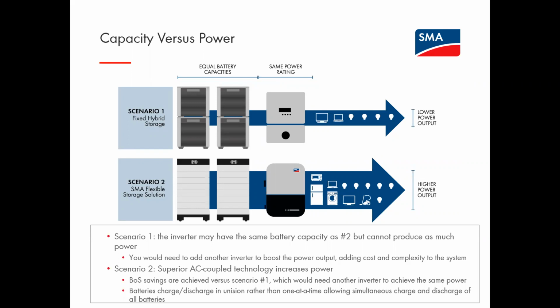So if you were to try to get more power out of the system, you would need a second inverter. In scenario two, the SMA flexible storage solution, both batteries can charge and discharge in unison, thus allowing us to extract instantaneously more power out of the battery system, which is certainly more important when you're designing a system to really provide a meaningful amount of backup power.